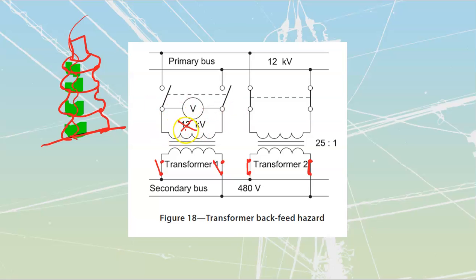And when Hydro comes around to fix whatever that problem is, those Hydro linemen can get a shock off that. They will track that down pretty quick, and they do it just by cutting off people's connections until they get rid of that connection. They'll remake the connections for everybody that wasn't backfeeding the system, but the poor sap that was backfeeding the system is going to have to wait a long time and deal with a lot of paperwork before BC Hydro gives them power back. All right, just be careful in your own operation that you do not get bit by this backfeed thing.